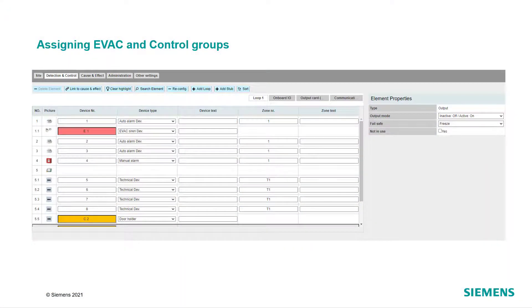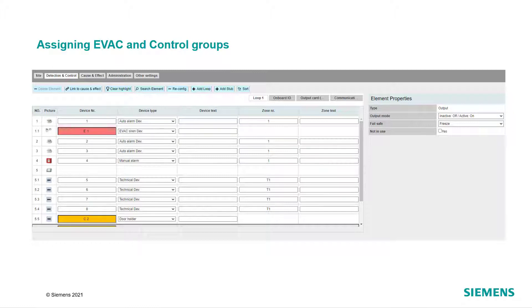For the configuration of controls, connect to your panel and select the Detection and Control tab. In Cerberus FIT, each sounder or control output must be assigned to an evacuation or control group.